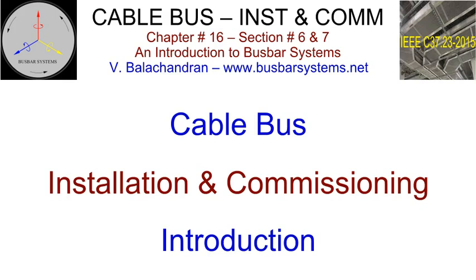Cable bus. Installation and commissioning. Introduction. Installation. A cable bus is a site-assembled product. Installation shall be strictly carried out as per the approved quality assurance plan for installation and commissioning. The activity shall be carried out under the supervision of certified and qualified personnel who are familiar with the product and safety norms. Only some of the major activities are detailed to ensure correct installation.